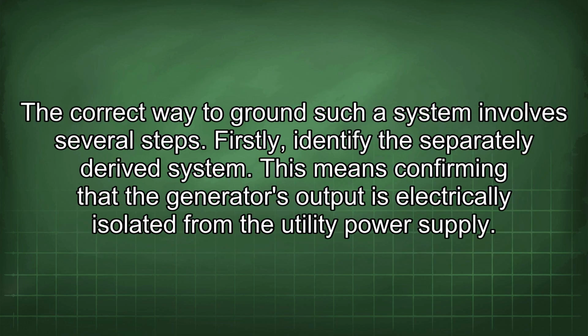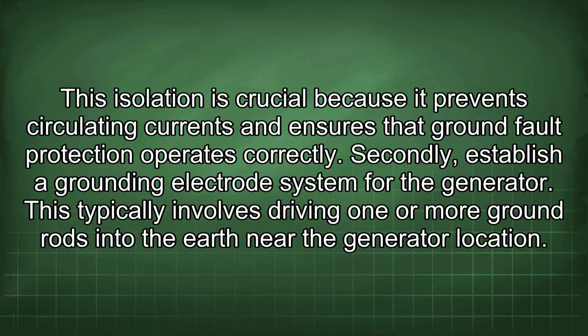The correct way to ground such a system involves several steps. Firstly, identify the separately derived system. This means confirming that the generator's output is electrically isolated from the utility power supply. This isolation is crucial because it prevents circulating currents and ensures that ground fault protection operates correctly.